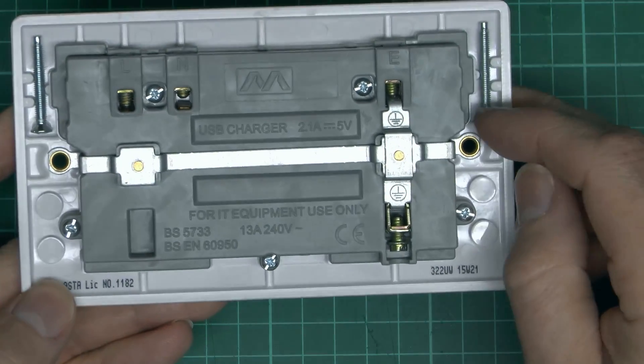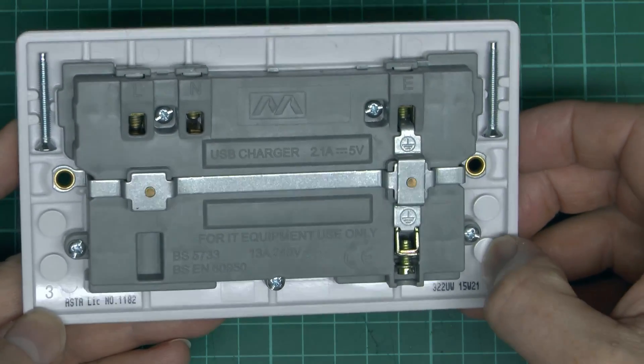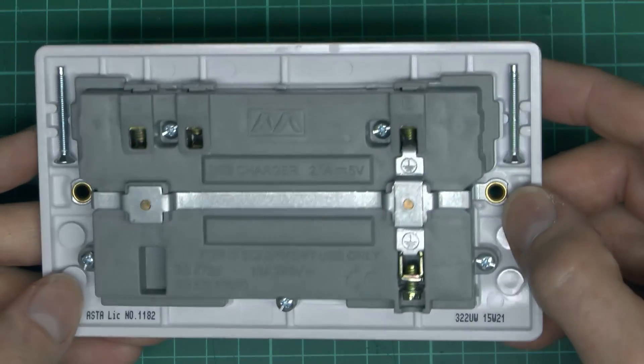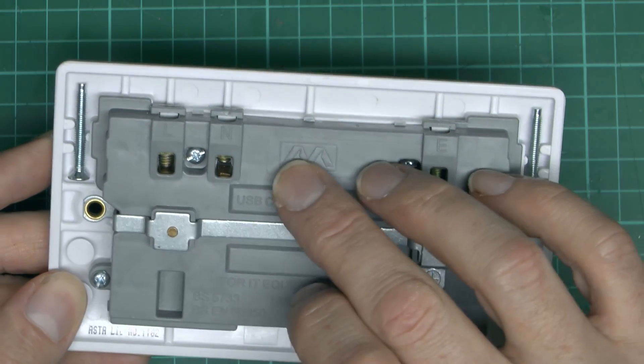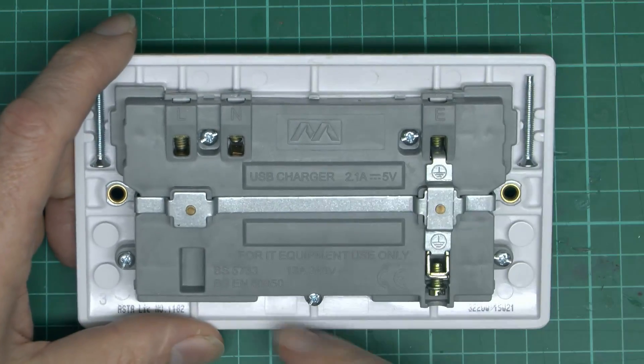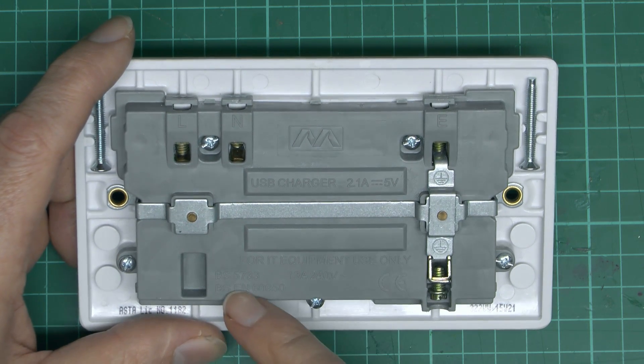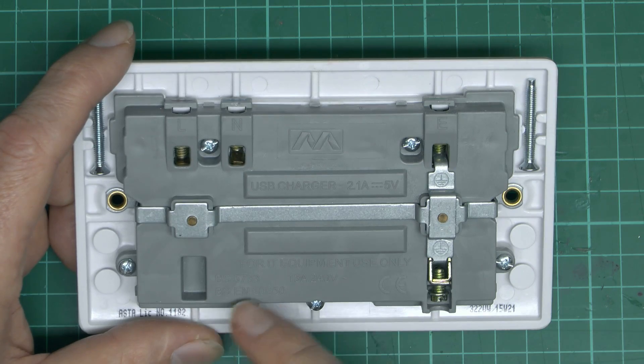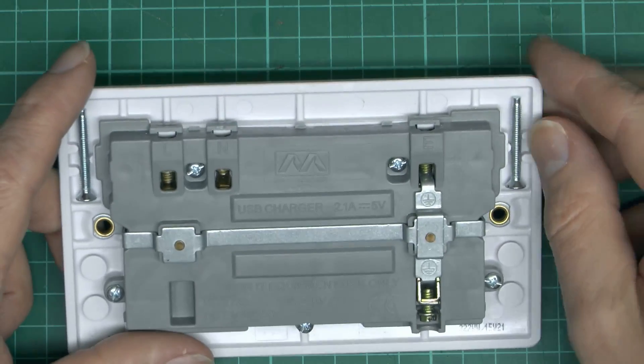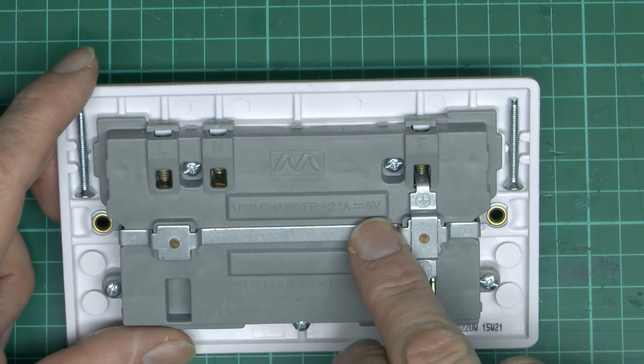Have a look on the back here. They didn't use the screws that came with it - presumably just used the screws from the previous socket - and they didn't use the screw caps either; those are supposed to go over the screws for people who don't like looking at them. The manufacturer on the back is actually Master Plug - that's their logo there. It says 'for IT equipment only,' 13 amps, 240 volts. The two standards listed are BS 5733 and BS EN 60950. 5733 is for general electrical accessories, and 6950 is for the IT equipment. USB charger: 2.1 amps DC, 5 volts.